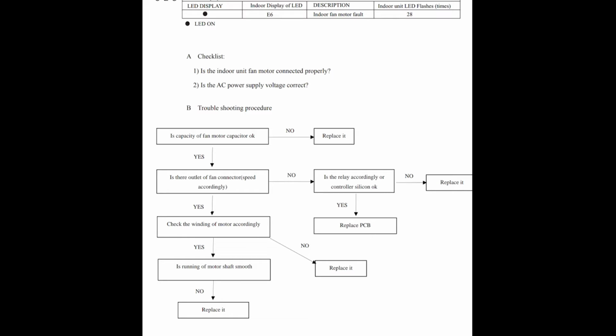So if your fan comes on, like I'm going to show you in this video, then there's nothing wrong with the fan motor. There's a problem with the main PCB if it only works in one mode and the other mode doesn't. Take into consideration that it does take around 5-10 minutes for the indoor coil to build up heat during the heating mode for the indoor fan motor to run. So if you put the mode in heating, the fan motor indoors is not automatically going to turn on. It has to build up coil temperature to a certain standard level before it turns the fan on. And you're going to notice in this video that I'm explaining all that to you so you have the information you need.